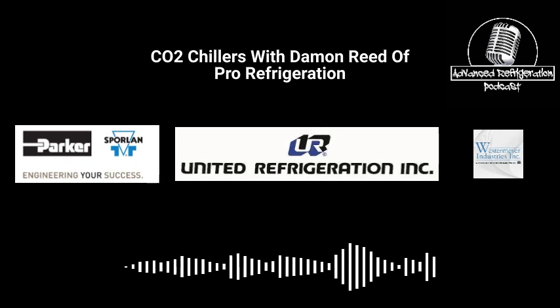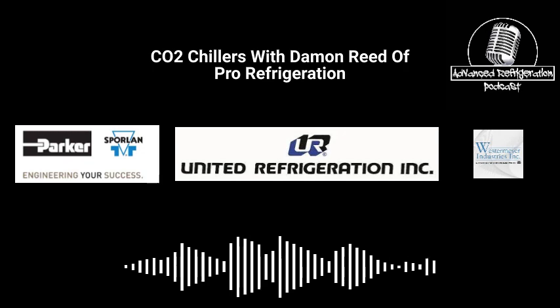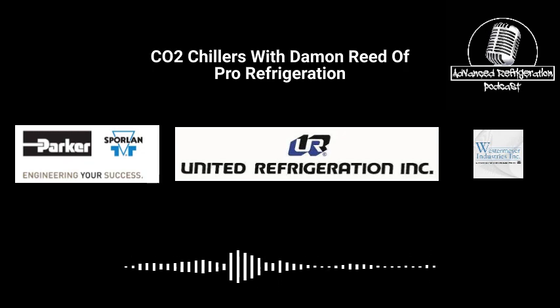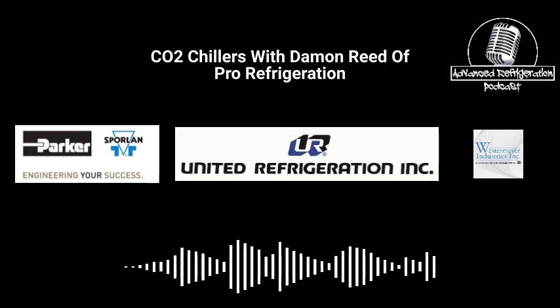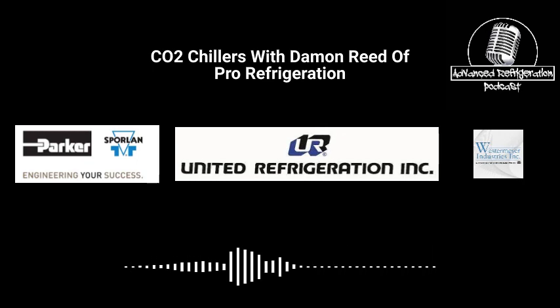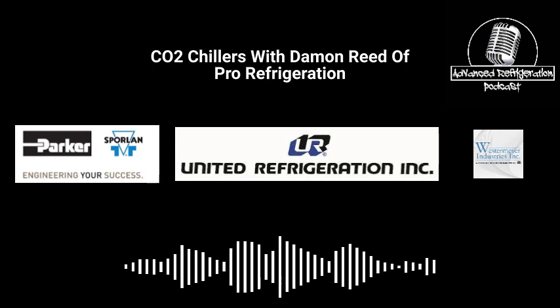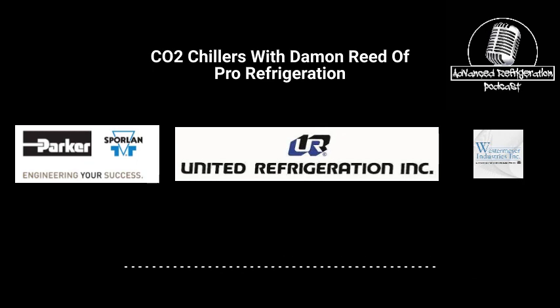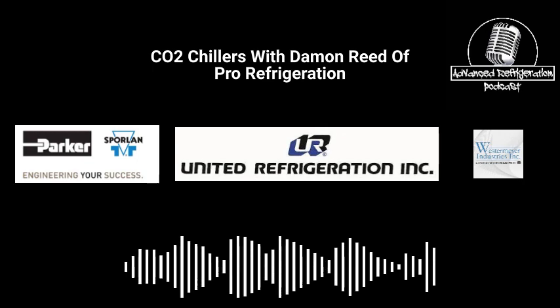Okay, but how many BTUs are you doing on these chillers typically? I'm doing close to around 700,000 BTUs per hour. So that's like two racks on a Super Target. Yeah, usually they're like 350, 400,000 BTUs per rack. That's a lot.